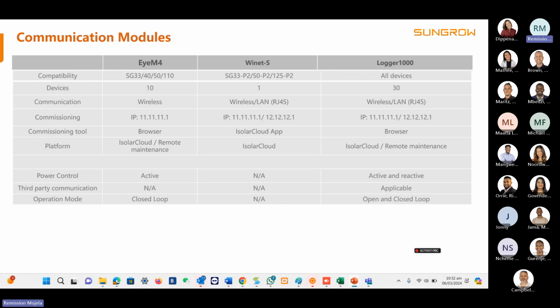The EyeM4 is good if you only have these inverters and you're not going to do any generator integration. It will just be the inverters with the grid and a meter. It will control them and you still have access to them. But just remember that it only takes up to 10 devices and that includes the meter. Just like the Logger 1000, it takes up to 30 devices and that includes the meter, meaning it's 29 inverters and 1 meter. The EyeM4 only has closed loop operation. Closed loop operation is continuously getting set points from the meter itself. With open loop, you just tell the system to produce a constant amount of power and it produces that. But with closed loop on the Logger 1000, it still looks at the meter and produces so as to avoid feeding back to the grid if you are doing zero export.